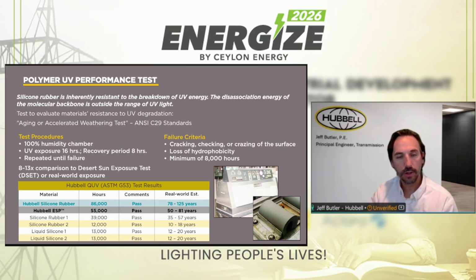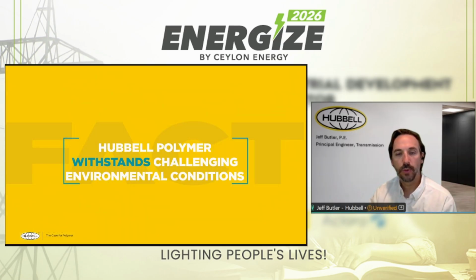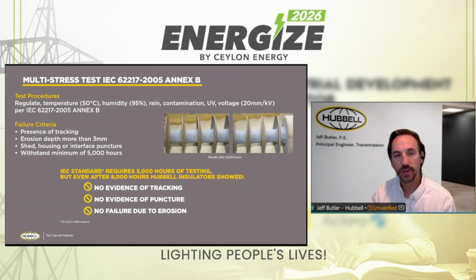We're just saying that, all other things put aside, UV exposure alone, that would be the estimated lifespan for the rubber. So furthermore, we looked at how to evaluate additional environmental conditions. As I was just saying, that previous test was basically just a UV exposure. So IEC has a multi-stress test that was defined back in 2005 in the standard IEC 62217. It's located in Annex B, and it's referred to as the multi-stress test. And the multi-stress test controls temperature, humidity, rain, contamination, UV, and voltage exposure.